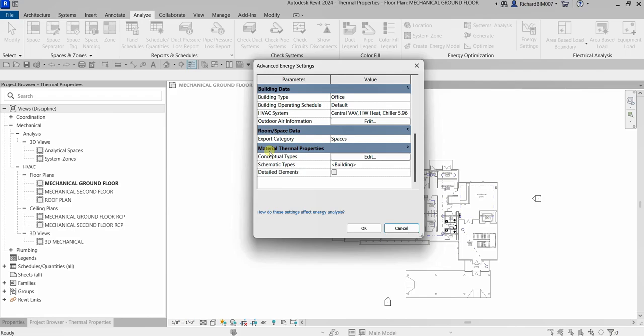Revit offers three ways to specify material thermal properties of building elements for energy analysis. First, we have Conceptual Types, which is the default. The next one is Schematic Types — if this is enabled, it will override the Conceptual Types. The third is Detailed Elements — if enabled and if material thermal properties are specified for building elements, it will override both the Conceptual Type and Schematic Type.